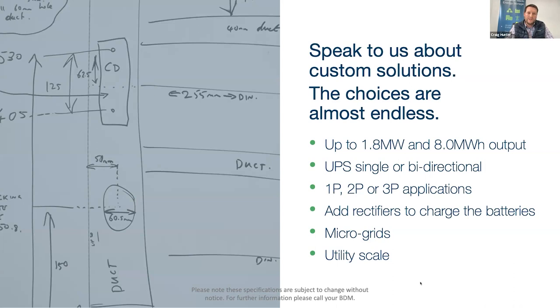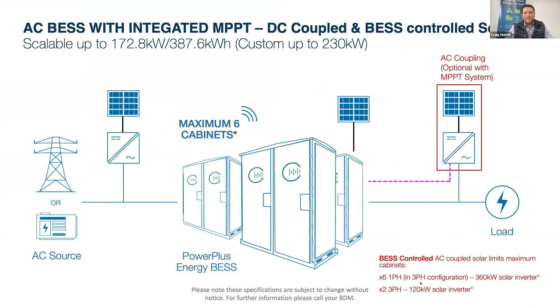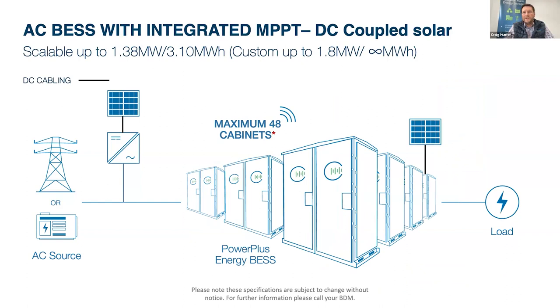When we look at scalability and configurations, I was saying before, if you wanted to have controlled AC coupled PV connected to the BESS where we're in control of it, you can go to a maximum of 6 cabinets of this, and that's where we scale out at the 172 kilowatts and around 400 kilowatt hours of storage. However, when we get to the more sizable systems, we can scale up to 48 of these cabinets connected together, and that's how we get up to that sort of 1.8 megawatts in size and around the 8 megawatt hours of storage.